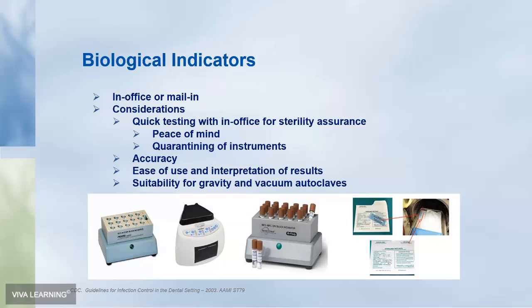It's essential that a monitoring log is kept. If you don't keep a monitoring log and there are any issues, it will be assumed that you did not do so. It needs to include the load number and the sterilizer number, serial number, particularly if you have more than one. It should contain the contents of the load and all of the monitoring results. That would include each time results of mechanical monitoring, chemical monitoring, and biological monitoring whenever it is performed. If you have printouts, they should be kept in the monitoring log. At the end, when you've got everything you need in that monitoring log, it also needs to be signed and dated by the operator.